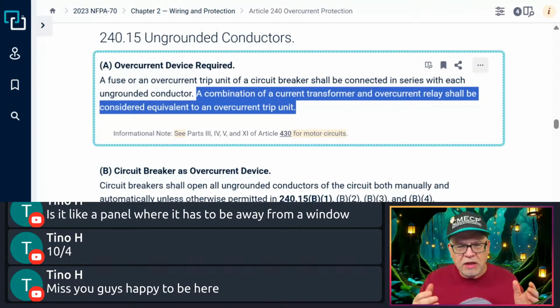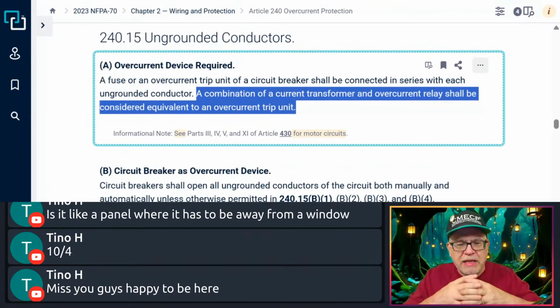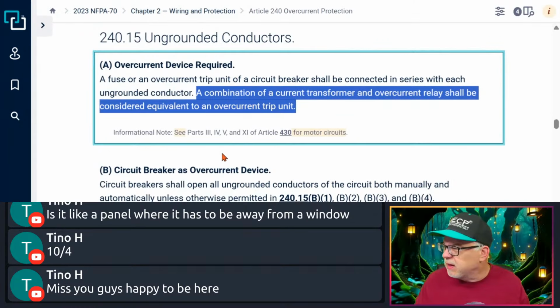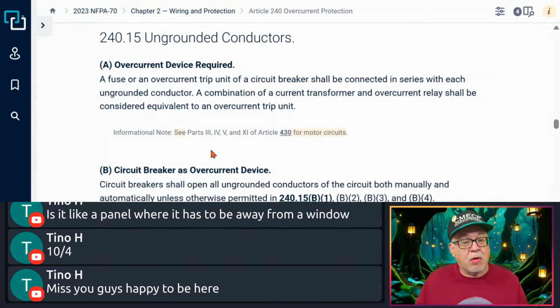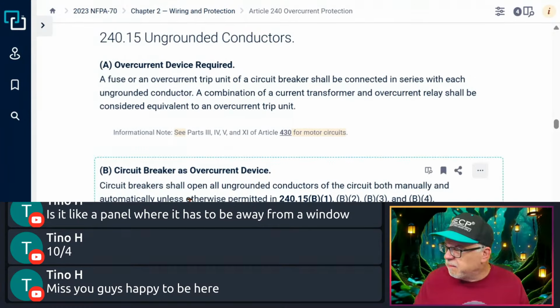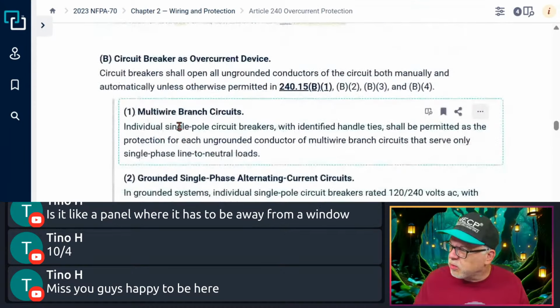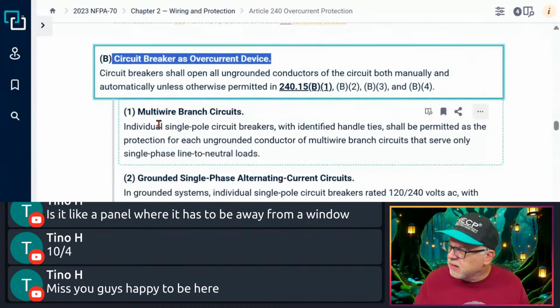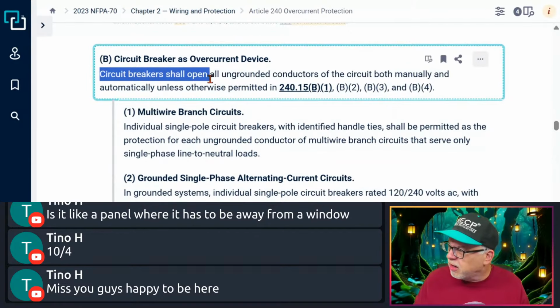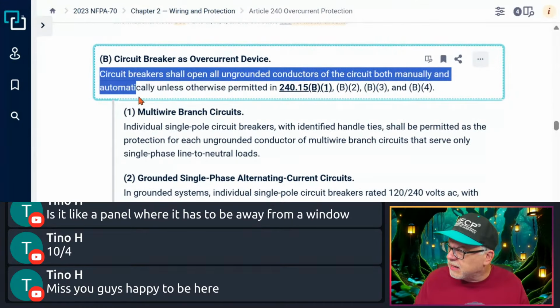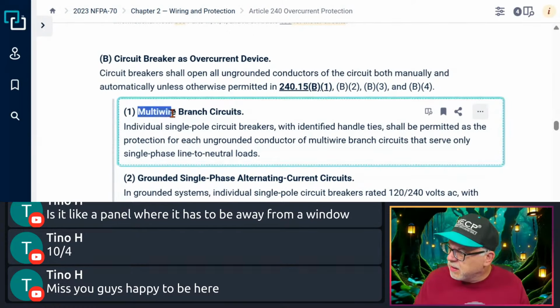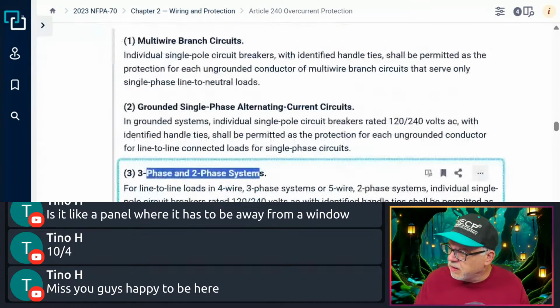Okay, so the question is, is a relay the same as an overcurrent device? No, it's not the same as an overcurrent device. When used in conjunction with a current transformer, okay, then that would be considered equivalent to an overcurrent trip unit. But again, a lot of that is typically only found in motor applications or motor control circuits and things like that. While we're here, by the way, you see this where it talks about circuit breakers as overcurrent devices, okay? And it says a circuit breaker shall open all ungrounded conductors of a circuit both manually and automatically unless otherwise permitted. And we've got some allowances down here. All right, that type of thing.